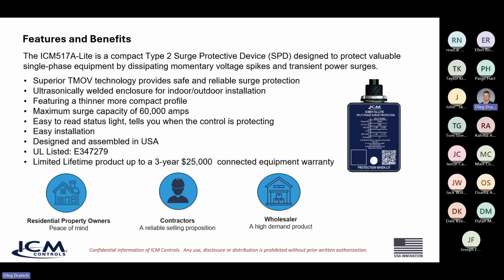Maximum surge capacity of 60,000 amps. That would be for one hit. If you had one massive hit up to 60,000 amps, you are protected with the ICM517A-Lite. There is a green status button right here where the laser pointer is. When that little window right there is green, when it's lit up, you have protection. So it's very easy to visually see that. Very, very easy installation. We've had feedback, and we've done it ourselves. It's 15 minutes or less, so it's very easy to install.